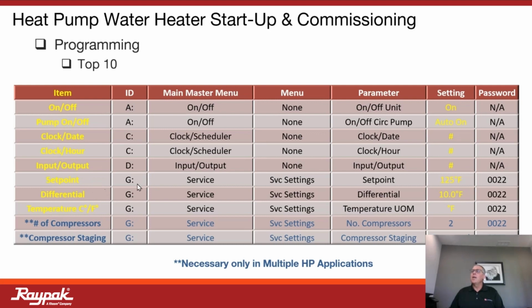Set point. Here is a set point. Very easy to access. This one is password protected. So we'll put in this password of 0022 and hit enter. And then we can go back and hit the up and down arrow. And if we're storing water in our tank at 140 degrees, we're going to adjust that set point up to 140 degrees, and off we go.